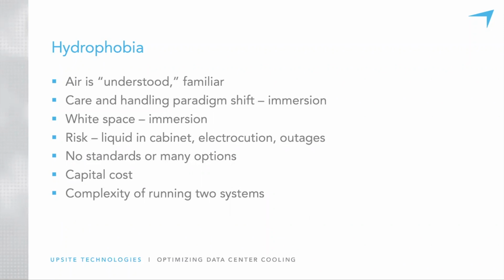One of the challenges with air is that it's invisible. You can't see it. So it's hard to know how many CFM are passing through IT equipment and how many CFM are bypassing the IT equipment. So there's a lot of opportunity left in airflow management for improvement and making that process more efficient and lowering cost. But it is familiar, and the data center industry is very risk averse. So they're not ones to necessarily jump on early adoption.